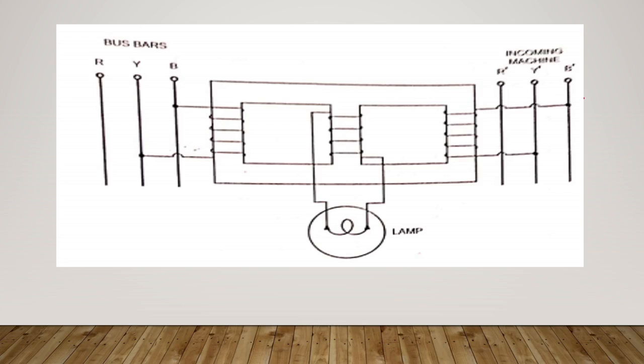If the phase sequence is known to be correct, the best method of synchronizing alternators is by means of a single phase device called a synchroscope, which will provide a more accurate indication of synchronism than lamps. So a synchroscope is an instrument for indicating the difference of phase and frequency between two voltages. It is a split phase motor in which torque is developed if the frequencies of the two voltages differ.